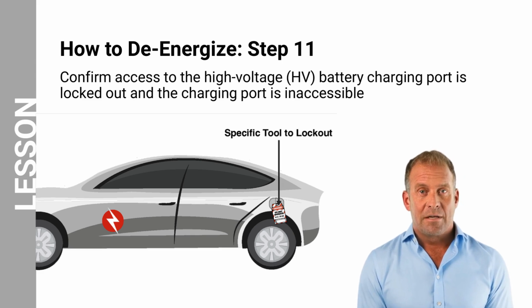Step 11. After de-energizing the high voltage system, verify that access to the high voltage battery charging port is locked out. This prevents accidental energization from external sources while the vehicle is unattended. Even with the high voltage system isolated internally, the charging port remains a potential point of access for external power sources.